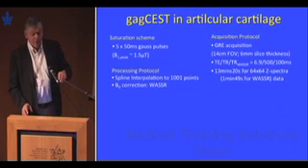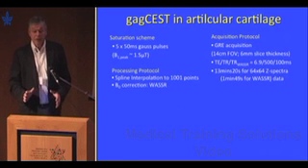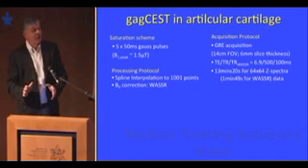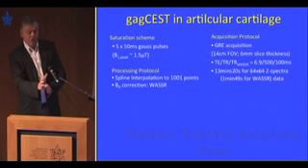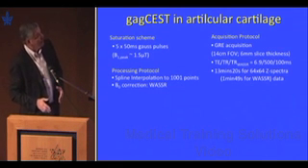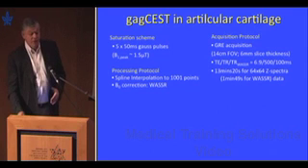So this is sort of the technique that we used. We wound up using a method that Peter van Zijl published on called WASSR to do the B0 correction. What you do is actually you do sort of a Z spectrum, pixel by pixel, at very high frequency resolution. You measure the center peak of water, you align everything up and do it. Again, it's a technique that's been published and just well described. And we use, in this case, a gradient echo acquisition. Later you'll see some fast spin echo acquisitions to start off with.